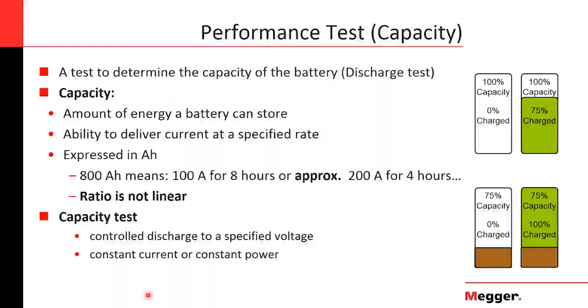The capacity test, again, is a controlled discharge with a constant current or constant power, and you drive the voltage of the battery to a specified voltage. The manufacturer will indicate the minimum voltage that you can discharge the battery to. As you discharge the battery and apply current, the voltage will start dropping, and you expect the battery to reach this minimum voltage at least at the specified time, like 8 hours or 4 hours. If the battery reaches that minimum voltage before completing the specified time, the capacity is reduced, and there's a formula to calculate that value.